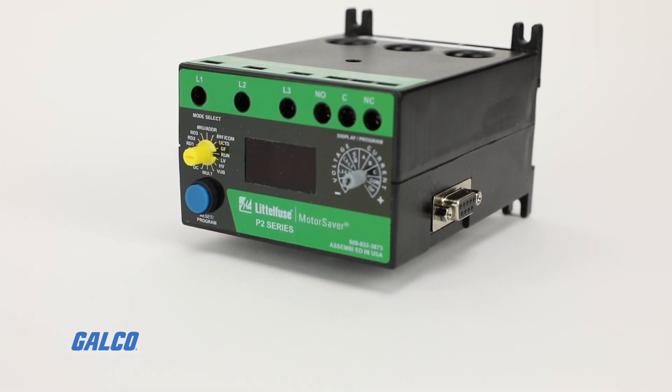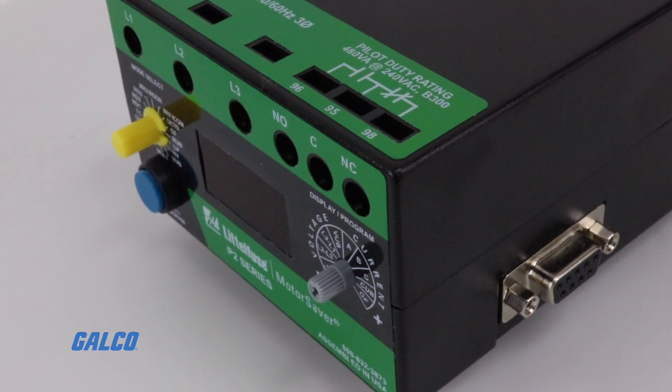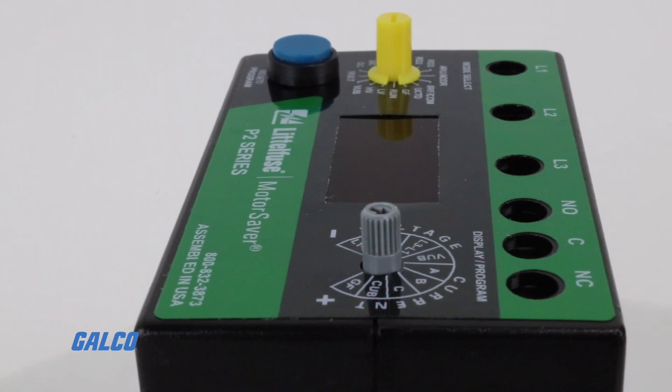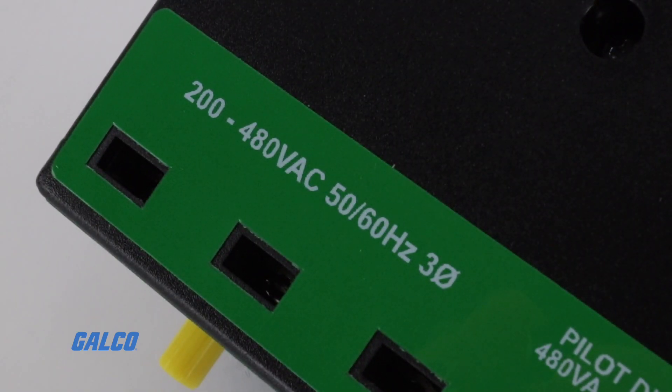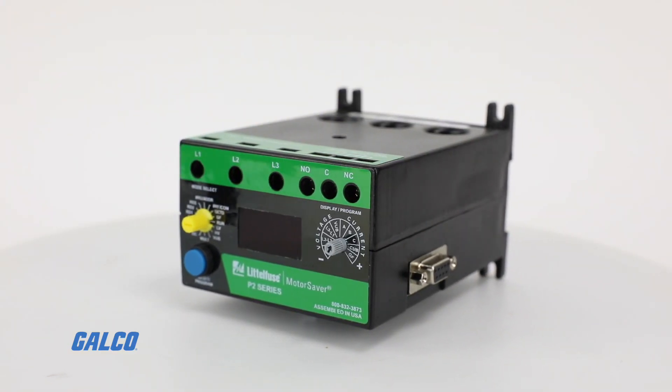SymCom 777 Series Electronic Overload Relay monitors current and voltage for superior motor protection. The 777 Series is designed for three-phase 200 to 480 volts AC applications, able to protect any motor that draws up to 800 full load amps.